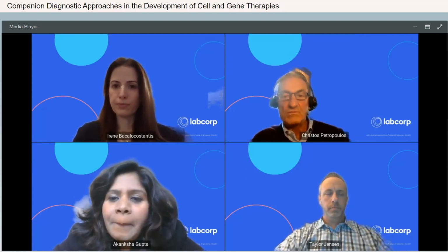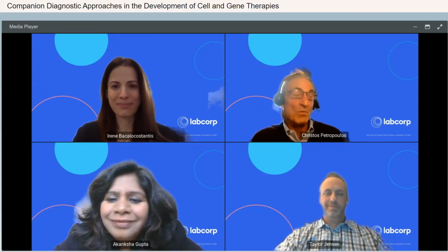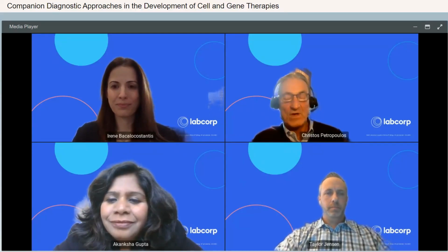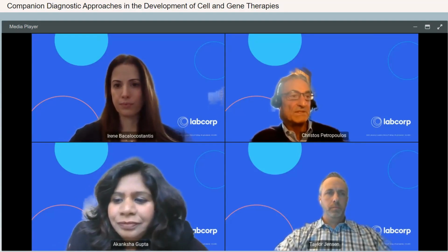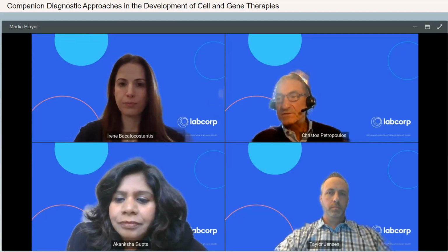And this all comes down to how well the assay performs around the assay cutoff, and what are those cutoffs. What keeps me up at night the most is what are the cutoffs based on very limited clinical data. You don't have a lot of clinical data to go on, and how do you set those cutoffs? And how do you understand the variation that you see around those assay cutoffs? Because the variation in the assay itself is not linear, and so you really need to understand the cutoff before you can describe the variation around the cutoff to the regulatory agencies that take that into consideration.